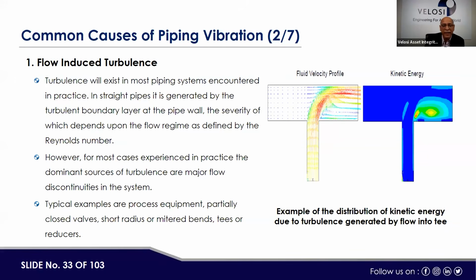Those are produced mostly at the bends, at structural discontinuity or flow discontinuity positions like elbows, T's, and orifice plates. There could be a reducer, valves. So all these aspects create turbulence, like a hindrance to the flow, and the hindrance of the flow is causing the turbulence, and the turbulence is causing the vibration, and vibration is causing a problem for pipe failure or support failure. Okay, now in most cases, as I explained earlier, turbulence is most on the flow discontinuities, which I described as elbow, T, bends, again the reducers and valves. Typical examples I also covered in my presentation.